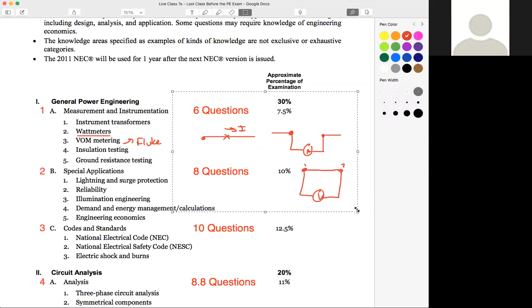Ground resistance testing - I like to stress all things grounding. For whatever reason, they just tend to be hot topics. Grounding is so related to safety that it seems like that's often tested on. So grounding is really important. Ground resistance testing - I don't know the number off the top of my head, and I believe it's in the NEC, but I could be wrong. But essentially, you're looking for a minimum ohm value. Michael Cook said 25 ohms. Awesome. Keena also said 25 ohms. You guys are on point. So you want to have less than 25 ohms to ground when you're doing ground resistance testing.